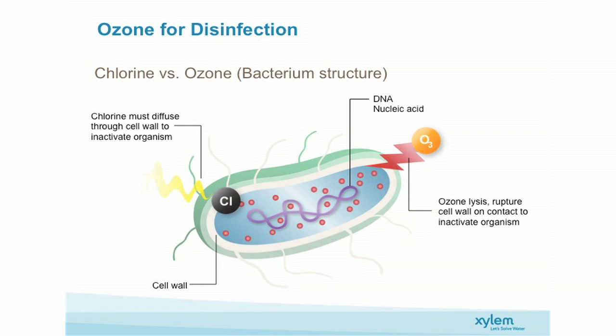How does ozone work? Ozone for disinfection is very effective because, unlike chlorine, which has to actually go into the cell before it disrupts and kills the cell or the organism, ozone actually oxidizes the cell membrane and ruptures the cell. You can't build up a tolerance to ozone. It's deadly on pretty much everything we know: spores, bacteria, viruses. So it's completely destructive to everything. It also operates about 3,000 times faster than chlorine, so your contact time and size of equipment is smaller.